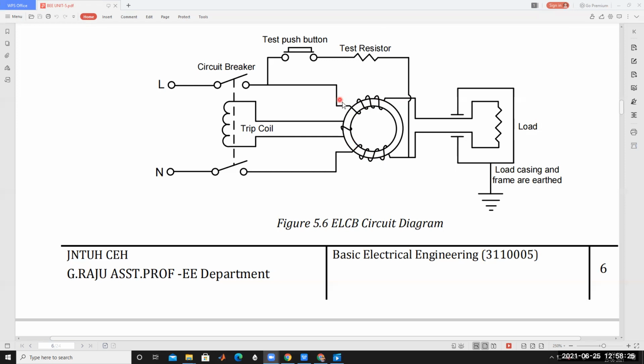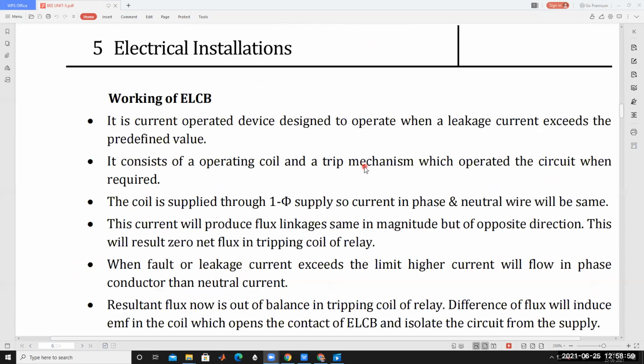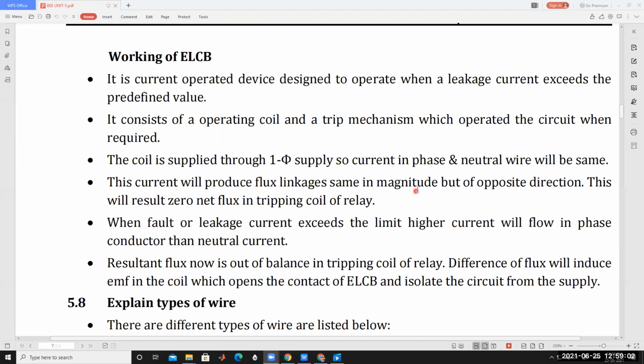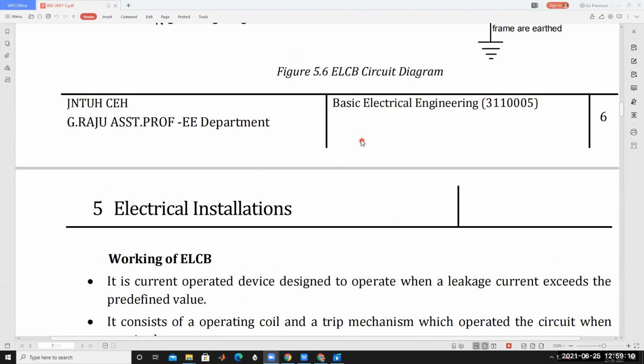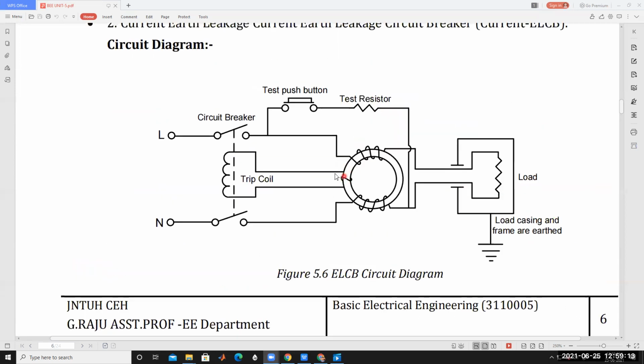Under normal condition, the current flowing to this winding and the current coming back are the same. For example, 10 amps comes in, flows to the load and comes back the same way: 10 amps here, 10 amps here. The two magnetic fluxes developed in the core are opposite each other, and the resultant flux is nullified, becoming 0. This current produces flux linkage of the same magnitude but opposite direction, resulting in 0 net flux in the tripping coil of the relay.